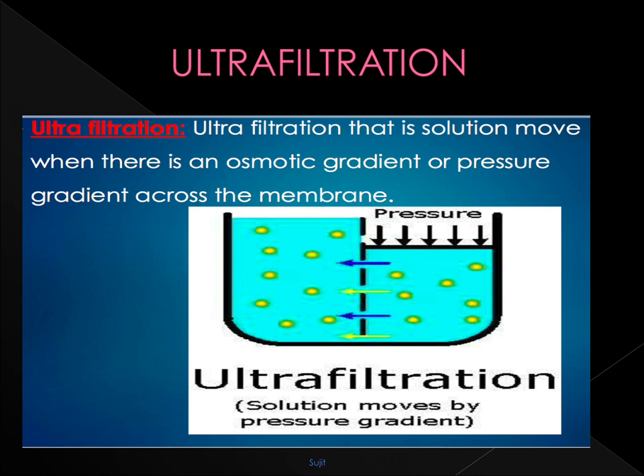Ultrafiltration is the movement of fluid through a semipermeable membrane along a pressure gradient, which may be an osmotic pressure gradient caused by glucose in peritoneal dialysis or a hydrostatic pressure gradient in hemodialysis. In hemodialysis, positive pressure is created on the blood side of the membrane and negative pressure on the fluid side. This positive-negative gradient influences the movement of fluid from the blood side to the dialysate side, resulting in net fluid removal from the patient.